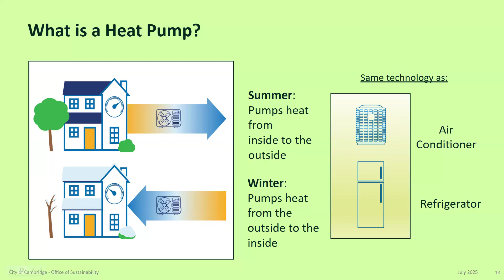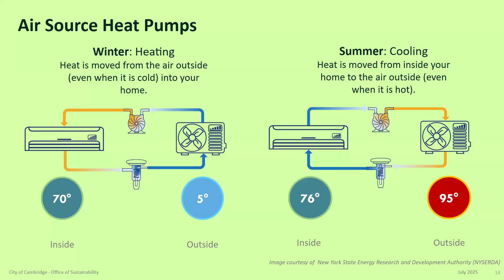Going back to what's happening in your heat pump system: air source heat pumps exchange heat energy with the air. It's possible to pull heat out of cold outside air because of the properties of the refrigerant. For example, R410A refrigerant—being phased out for a more environmentally friendly refrigerant starting in 2026 for new systems—boils at negative 55 degrees Fahrenheit. So even when the outside air temperature is negative 15, it's actually really warm for the refrigerant, allowing it to extract heat energy from it.